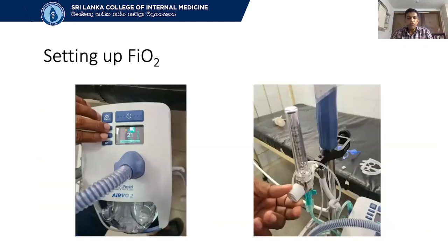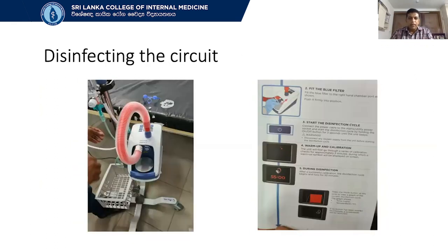Next thing, you go to the FiO2. So adjusting FiO2 is a different thing. You go to the FiO2 screen and then you change it with the flow meter. So you increase the FiO2 with the flow meter. Usually we start with about 30 to 40%. Then we can go up to 60% of FiO2. Usually you don't need that much. Right? So this is how you set up your machine, and it's very easy. Now, this is one thing that the nurses should do.